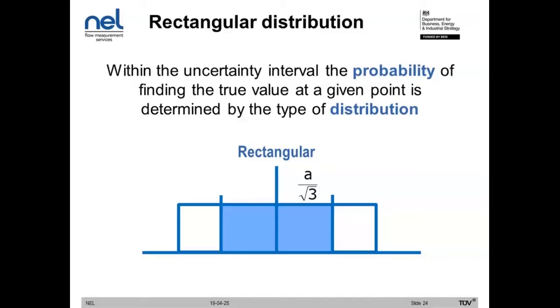So in this case, we have uncertainty based on this distribution. This is different from the standard uncertainty for a Gaussian or normal distribution. In this case, every value is just as likely as the next. So the A represents the limits of the range. The minimum value is minus A, and the maximum value is positive A. And the coverage factor in this case is square root of 3. So we'll see that in later examples.